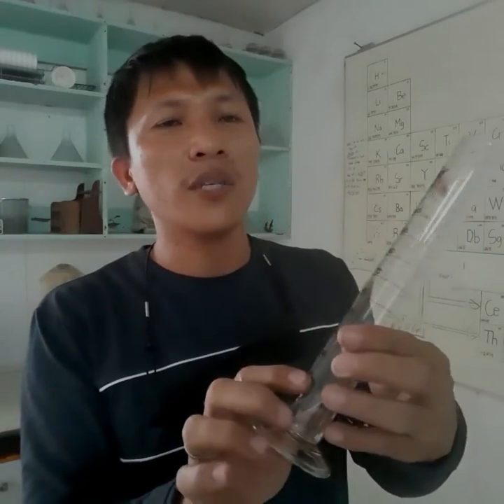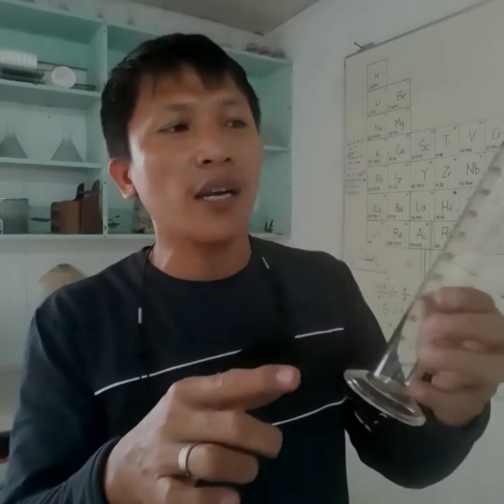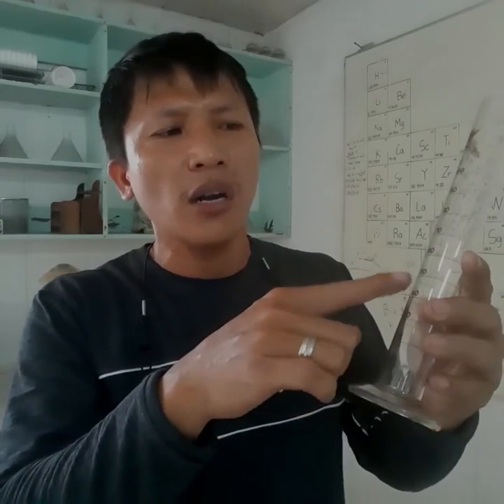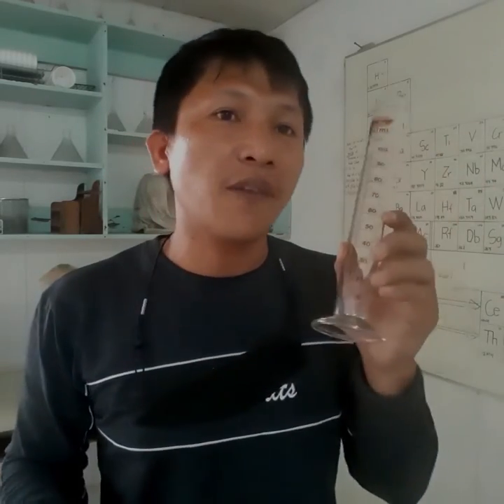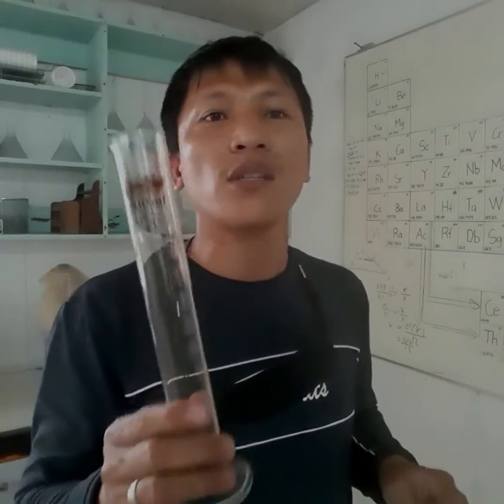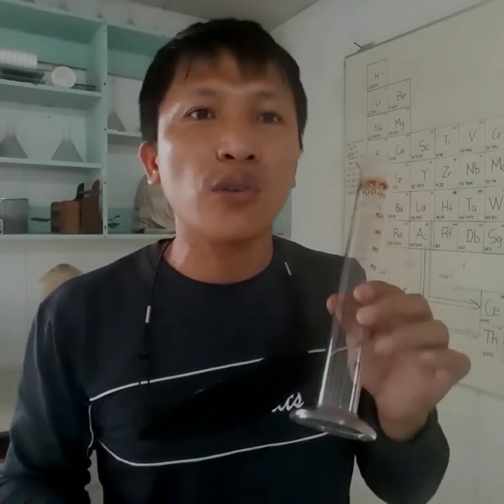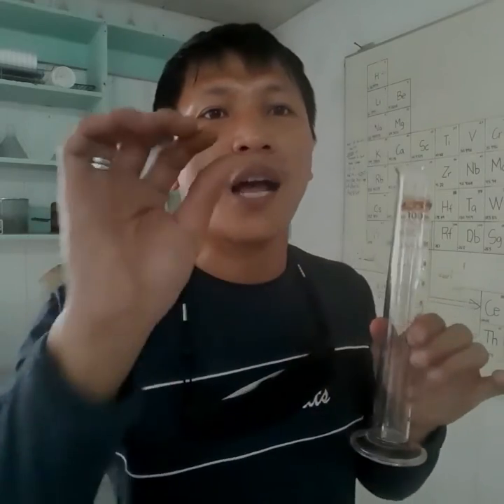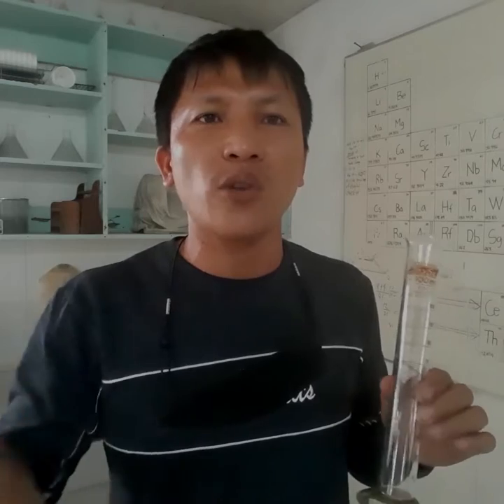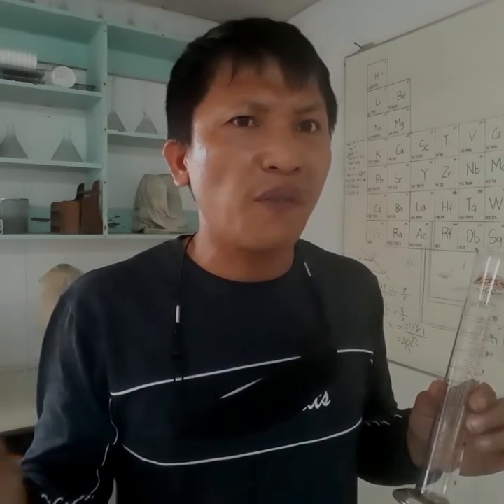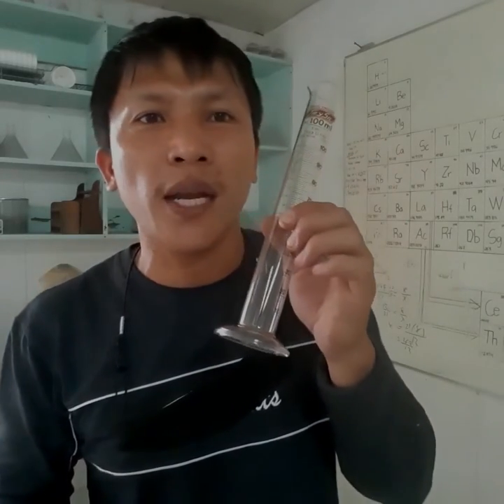This one can hold up to 100 ml, so you can measure up to 100 ml, or 50, 60, 70. But if you're going to measure 25 ml, you'd better use a smaller size graduated cylinder, because accuracy matters. If you want to measure 15 or 20 ml, use the 25 ml size rather than this bigger one, because the accuracy would be better.